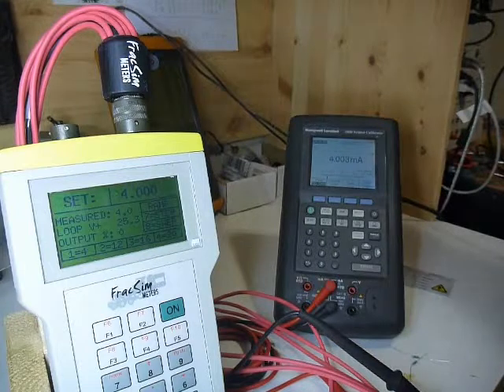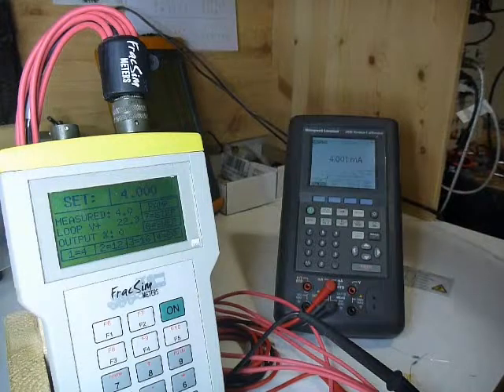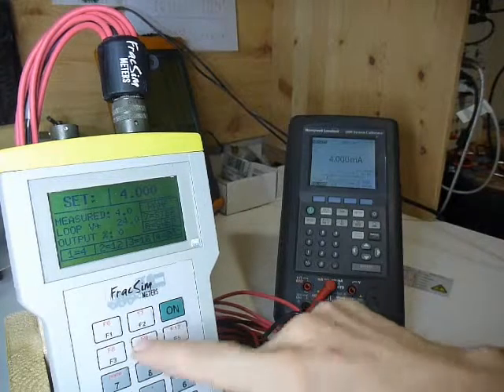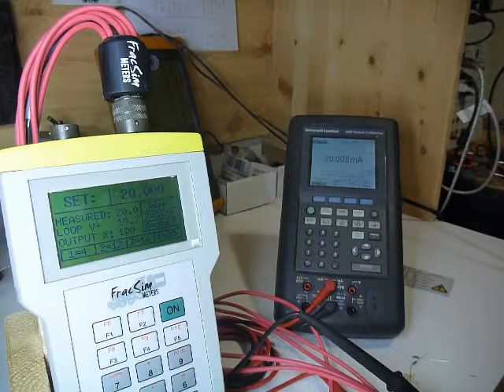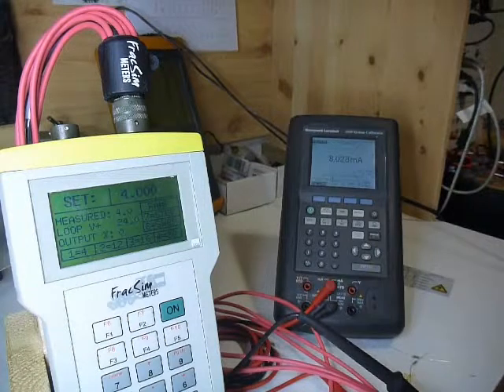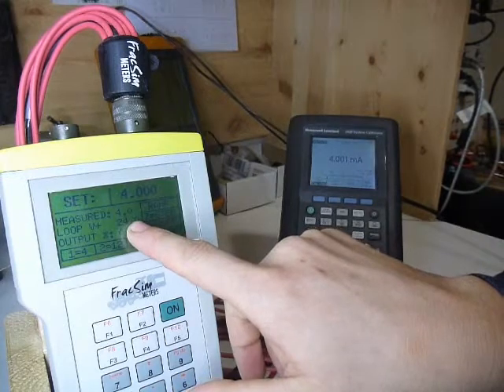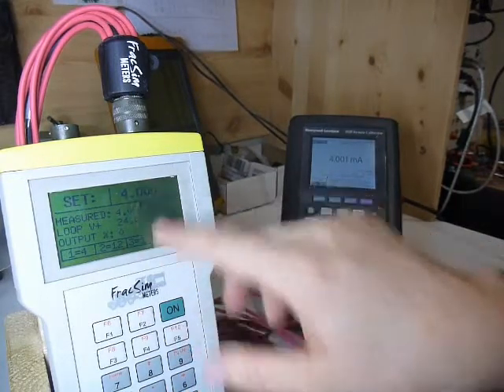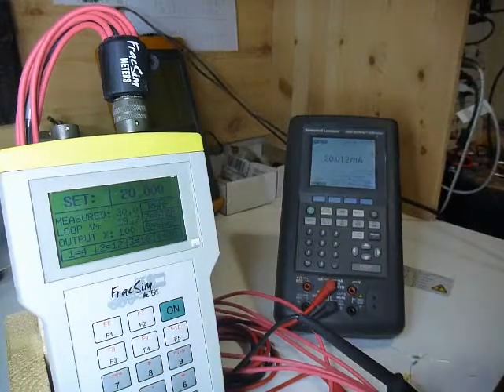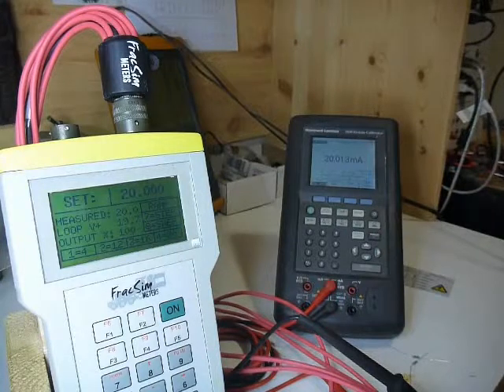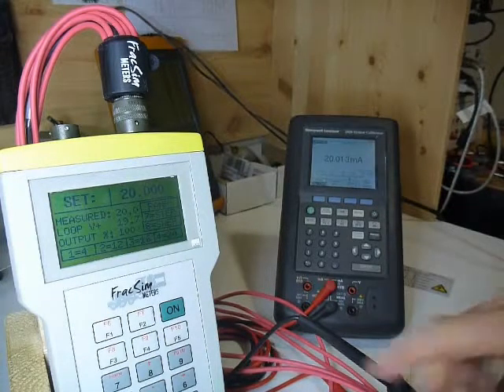And let me just drop this down to 24, we'll do this again. So 24 volts at 4 milliamps. If I go to 20, we got 20 volts now. That's because normally a 250 ohm resistor at a 4 milliamp load is a 1 volt drop. So really, we should have about 24 volts total right now because of that first 1 volt drop. Now if we went to 20 milliamps, on a 250 ohm resistor that would be 5 volts. So we should have a 4 volt swing, which we do approximately. We're getting about a 4.3 volt change.